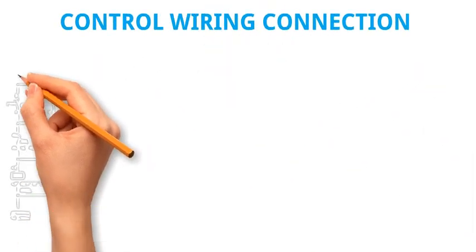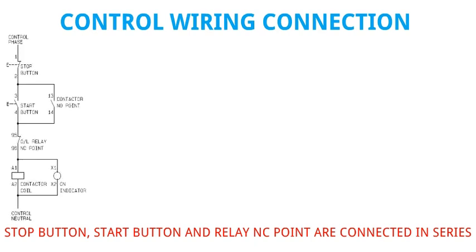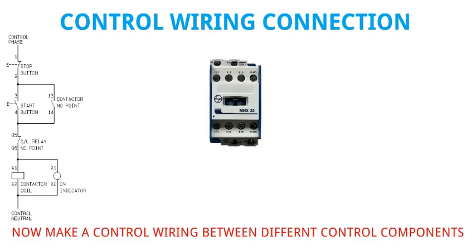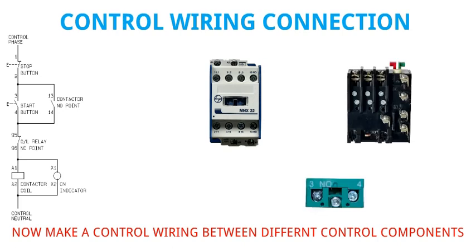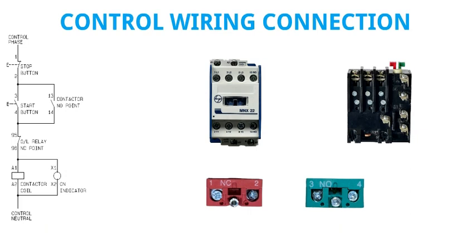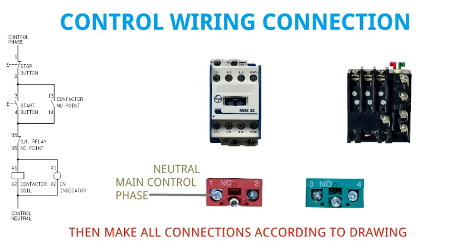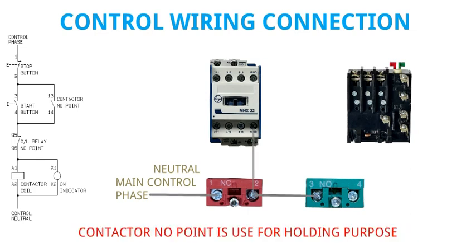Now look at the control wiring diagram. The stop button, start button, and relay NC point are connected in series. The contactor NO point is connected in parallel with the start button. Now make the control wiring between the different control components. Connect the NC element with the main control supply, then make all connections according to the drawing.